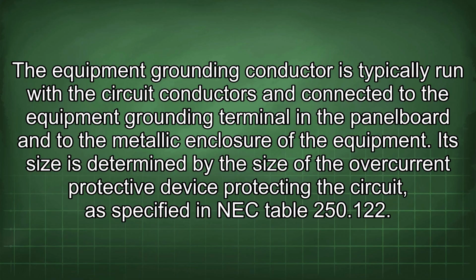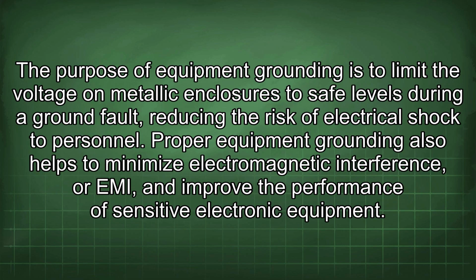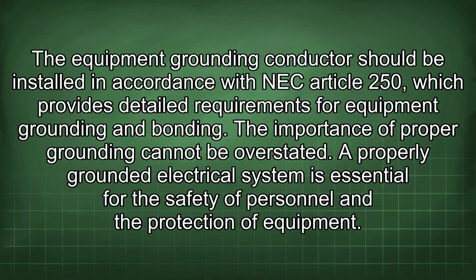Its size is determined by the size of the overcurrent protective device protecting the circuit, as specified in NEC Table 250.122. The purpose of equipment grounding is to limit the voltage on metallic enclosures to safe levels during a ground fault, reducing the risk of electrical shock to personnel. Proper equipment grounding also helps to minimize electromagnetic interference, or EMI, and improve the performance of sensitive electronic equipment.